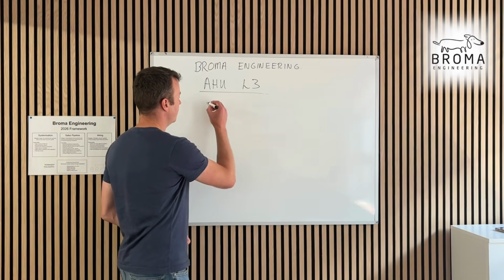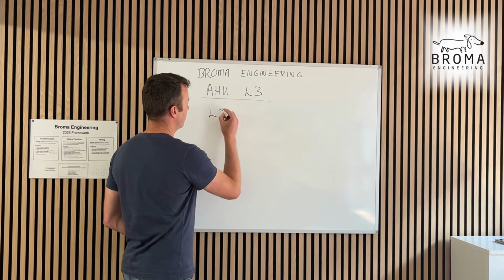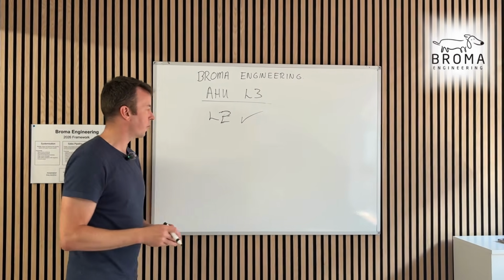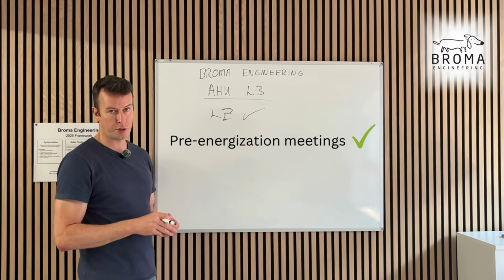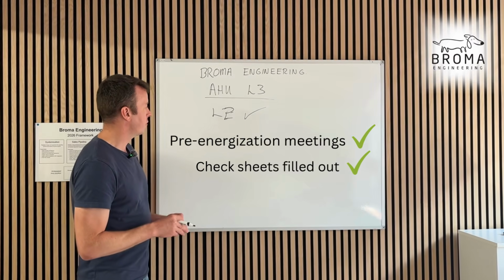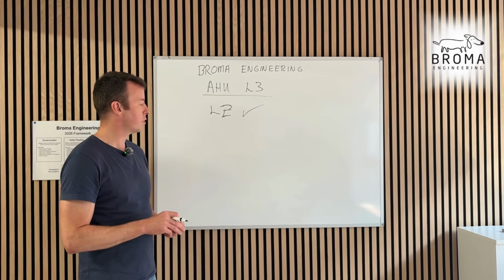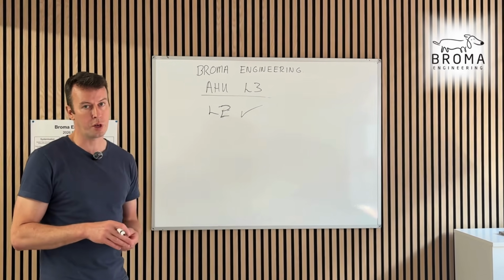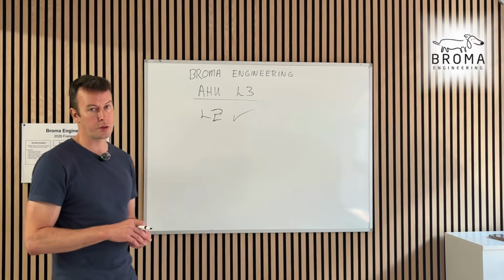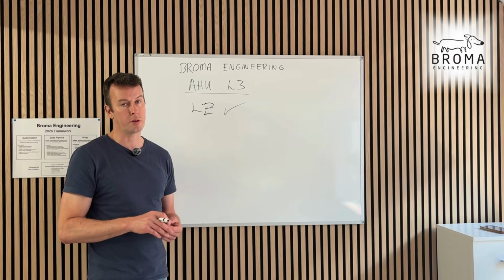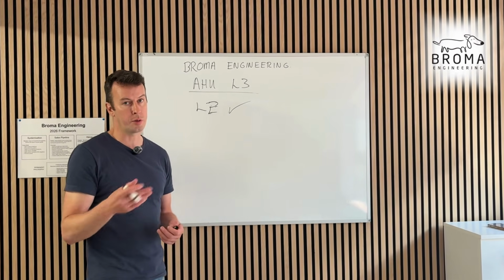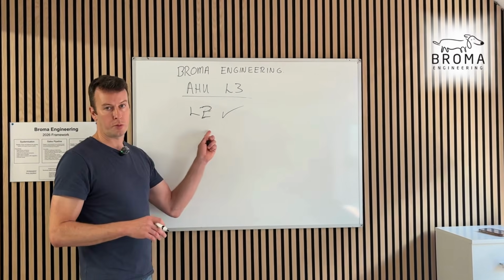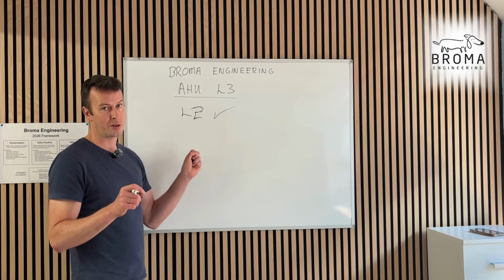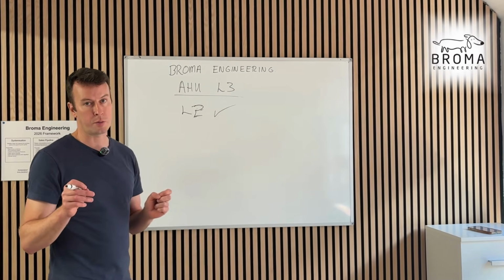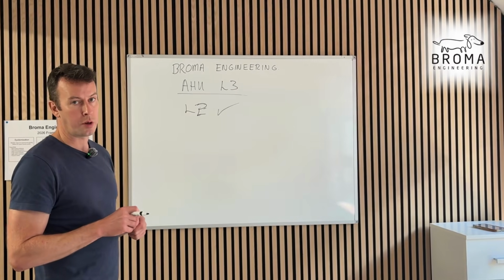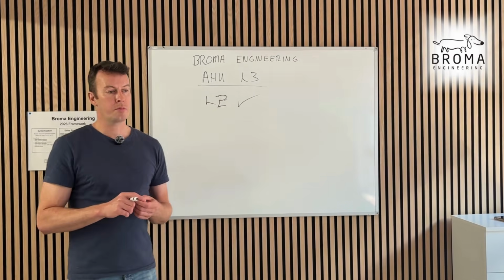Okay, so level 2 is complete. We've had our pre-energization meetings, everything's gone well, all check sheets are filled out, no major snags. Only critical or major snags should stop level 3. Any minor snags can be sorted out during level 3, level 4, level 5, and even after handover, there's a guaranteed period where you can fix snags. So don't let people stop you going ahead because of minor snags. Check the contract, always know your contract, check the specs, and make sure you're not being held up for no reason.